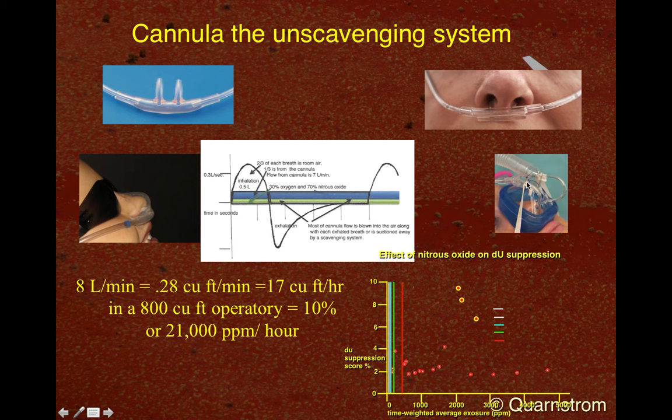They've got this hood and suction on this hose here, but there's a bunch of holes. So when the patient exhales, a lot of gas comes out of those holes. In situations using masks like this or this, it's been shown the dental office could have levels of nitrous as high as 3,000 to 5,000 parts per million if you don't have effective scavenging. I'm not very happy with either of these, and the cannula is a device that will bail you out sometimes if you're working in an area where you can't use a mask, but you wouldn't want to use it on a regular basis.